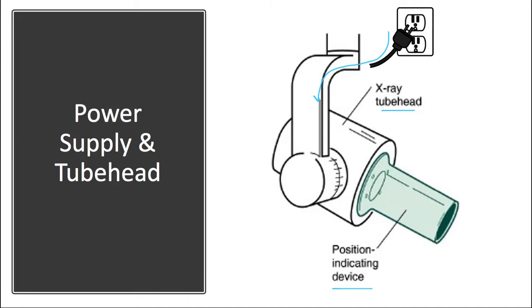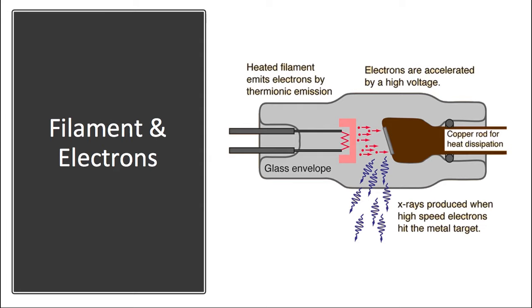The x-ray tube or tube head is the housing in which the actual x-rays are created. So let's take a look inside. We have a circuit that heats up a filament which burns off electrons. These electrons contact a tungsten target that produces the actual x-rays. This copper rod is used to dissipate the heat and a leaded glass envelope surrounds and insulates the entire assembly.